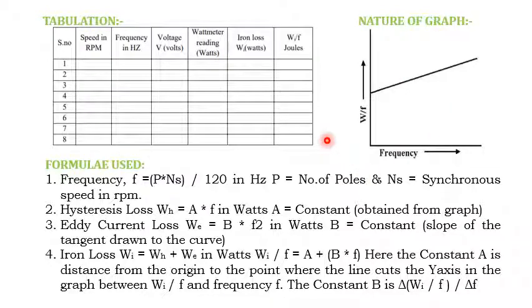Some formulas are used here. We calculate the frequency by using the formula P into Ns divided by 120, where P is the number of poles and Ns is the synchronous speed in RPM. Then the hysteresis loss is calculated by A into F, in watts. How do we obtain this A? A can be obtained from the graph. This is the A value.